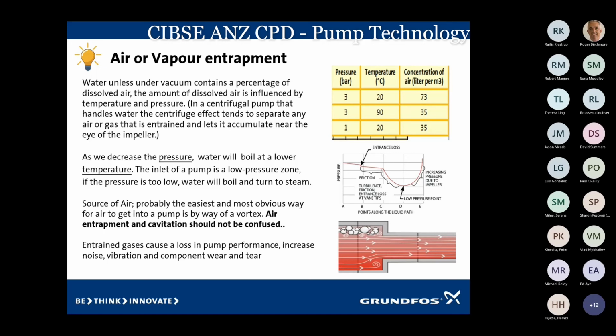When we talk about cavitation, a good way of testing a pump to see if it's cavitating is to get the valve after the pump and pull it back, just close it off. And if that noise goes away, then you know it's cavitation.